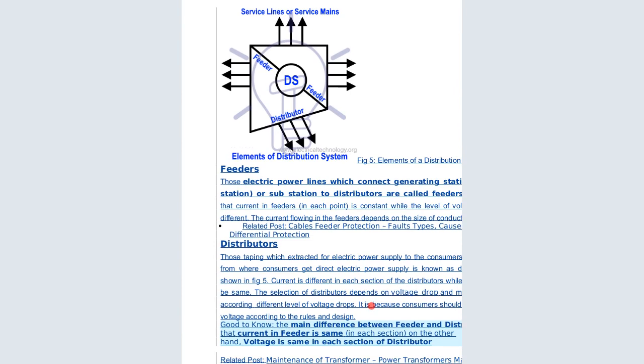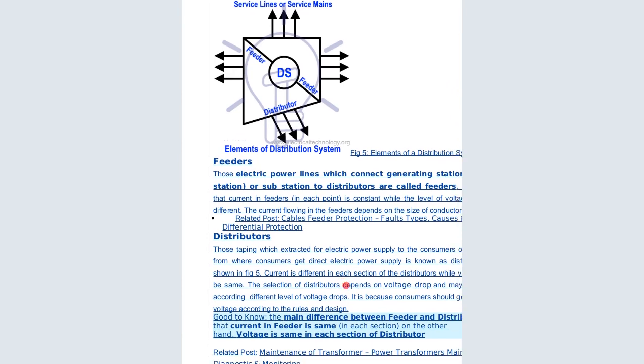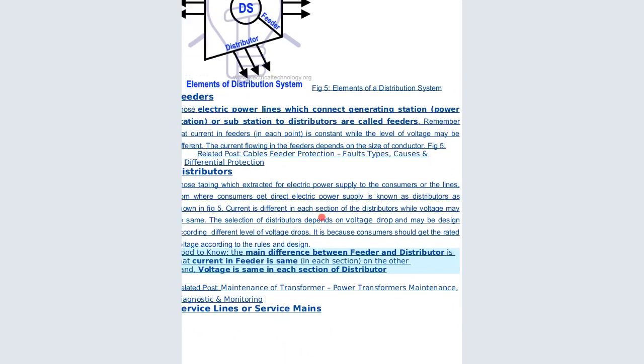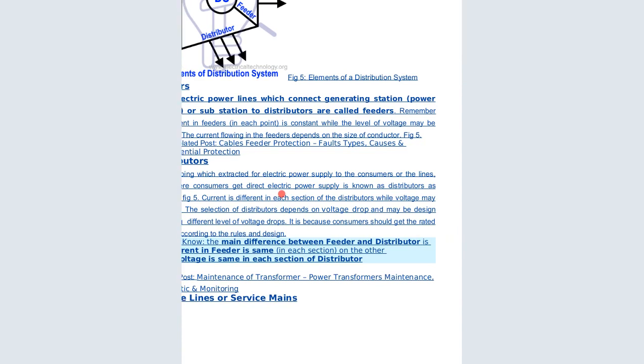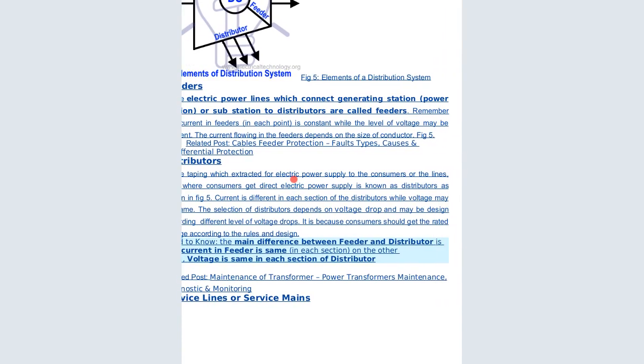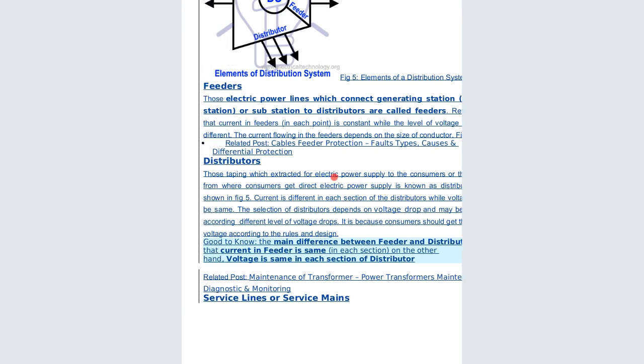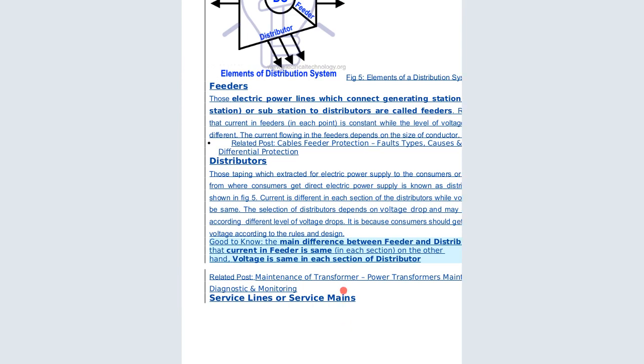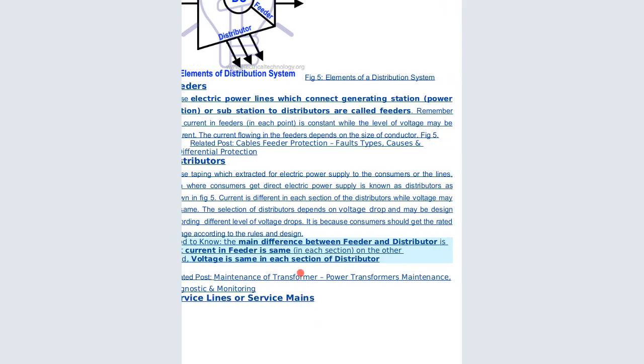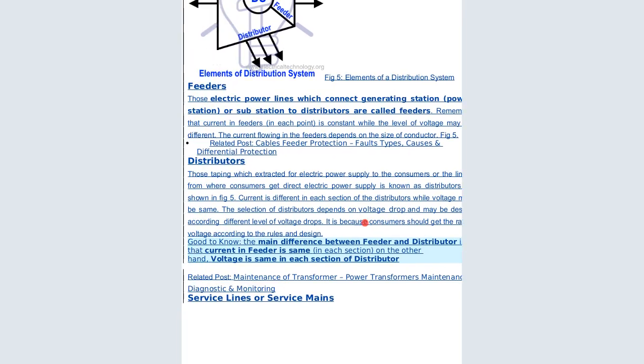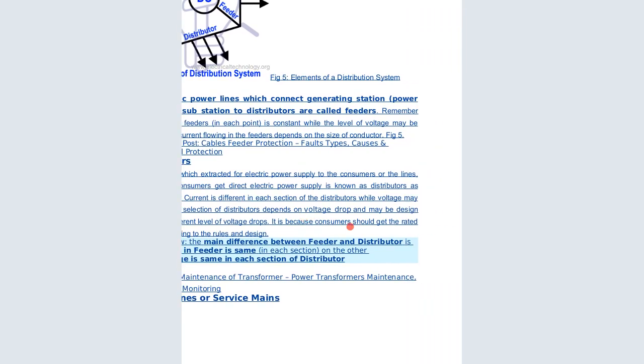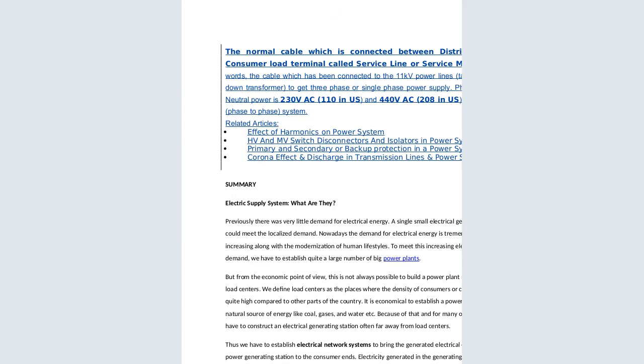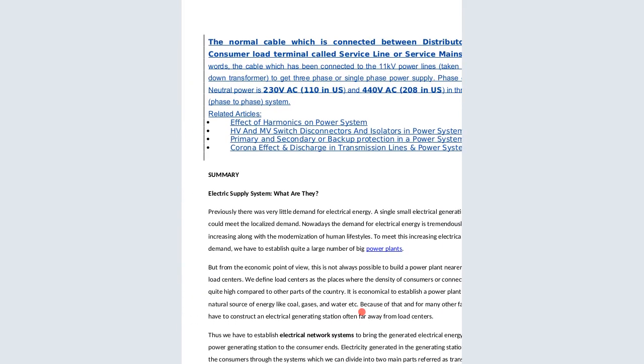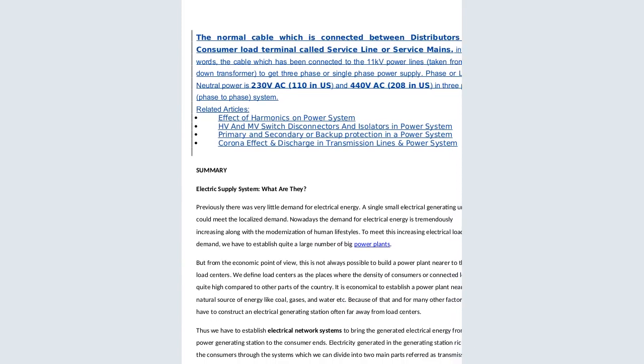So the elements of the distribution system are the feeder distribution system. A feeder is an electrical power line which connects a generating station, power stations or substations. Remember, the current in a feeder at each point is constant, while the level of voltage may be different. Then we have distributors, those tappings which extract the electrical power supply to the consumers, or the lines from which consumers get direct electric power supply, known as the distributors. Then the service lines are the service cables, the service mains. These are the normal cables which are connected to the distributors and the consumer load terminals. These are the ones that supply power to the consumers.